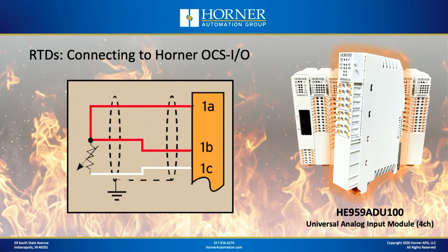How are RTDs connected to our OCS-I family through our universal analog input module? Well, you've got 3 leads on the RTD typically, and 3 leads for each channel of the ADU100. And effectively, the 2 excitation red leads connect to A and B, and the measurement white lead connects to C.